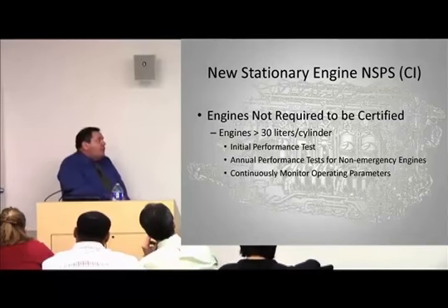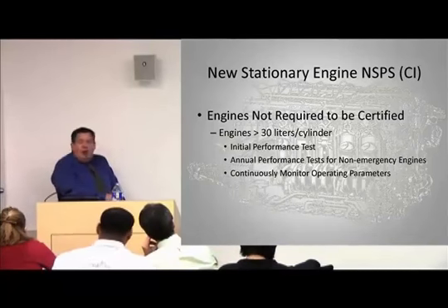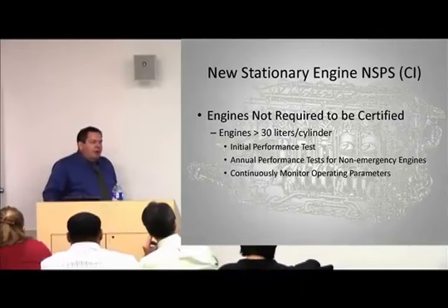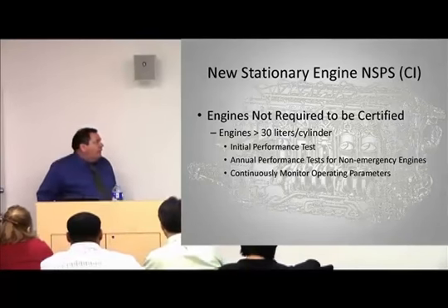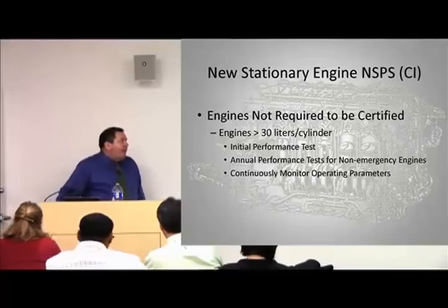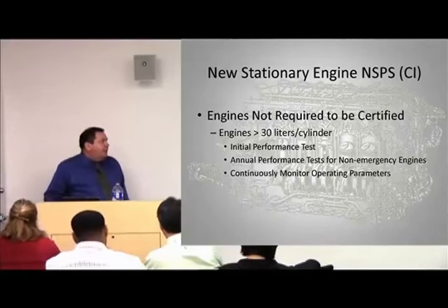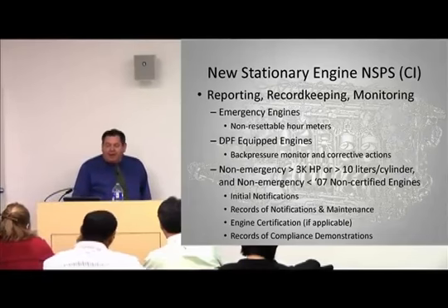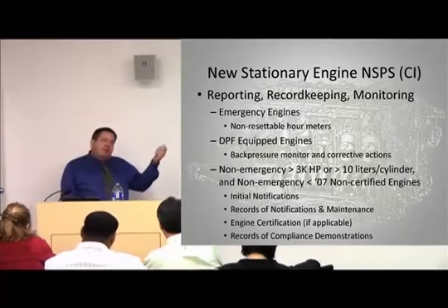For engines greater than 30 liters per cylinder, they're not required to be certified. There are standards for marine engines, but they're not the typical certificate of conformity like we see for non-road engines. So you have to do an initial performance test, annual performance tests for non-emergency engines, and continuously monitor operating parameters. That's the CMS that they mention in this rule.